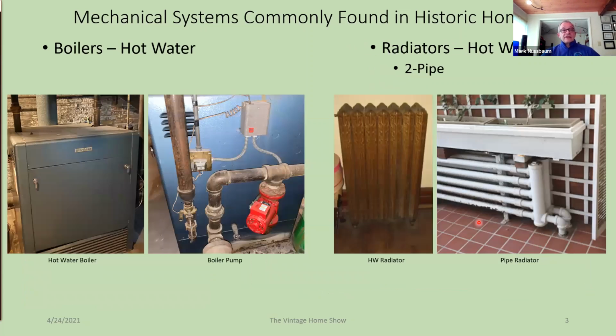And then you have hot water boilers that produce hot water that's usually circulated around with a pump. These days, it's usually circulated. Back 100 plus years ago, it was fairly common to have a gravity system, which used the buoyancy effect of hot water. So there was no circulator. It was a very quiet, very expensive system because you had huge piping that you had to install, because there was no motivating force other than the temperature difference to drive the water around. Those radiators, of course, are two-pipe radiators, always with a supply pipe in and a return pipe out.